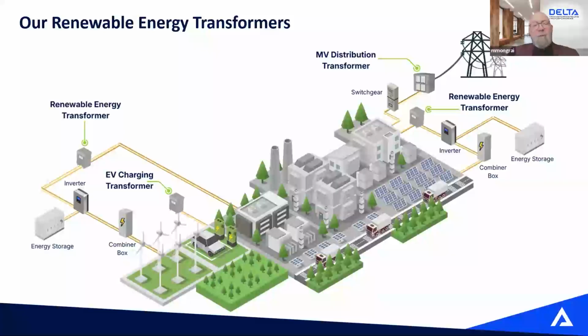Depending on which side is going to be energized, if you energize by your secondary side, you energize by the coil that is the closest to the core. So you're going to increase this inrush probably by 2 or 3 times. So you may end up with 25 to 30 times your nominal current. So that's one thing. The other thing that is important is your full capacity adjustment taps. On which side do you want them? Usually we put those taps on the primary source.